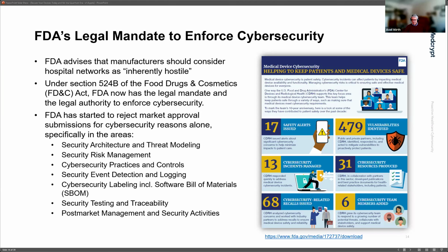Right, so FDA expects that your tests confirm that the identified risks, the risks you identified during design, are addressed through the appropriate controls, and that you can confirm through testing that those controls are working. And then the same is also true for your security requirements. Demonstrate that they're implemented and demonstrate through testing that your implementation indeed meets the core requirements for cybersecurity.